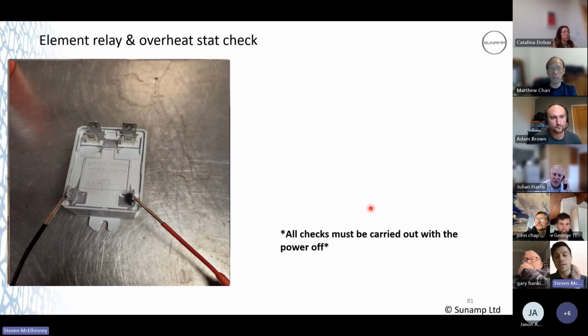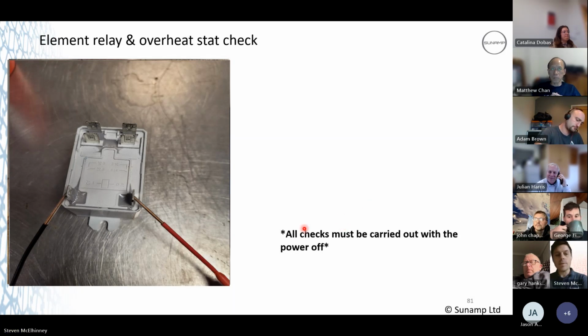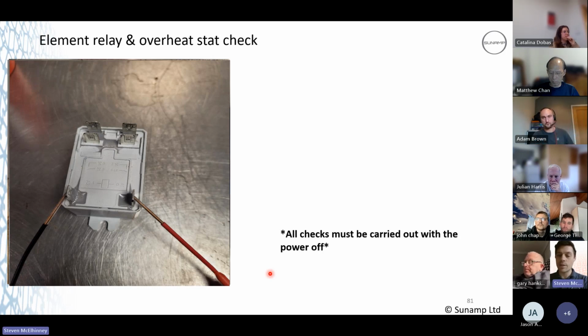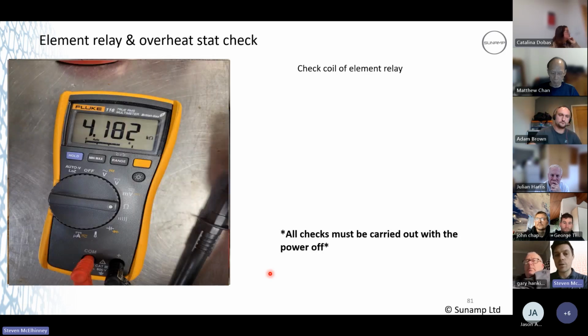Checking, so this is actually an AC relay. All our units now will be supplied with the DC. It's just in case you come across one of the older units, it may have a white relay in there, which is AC powered. So, how to check it? Obviously it's just got a coil in there. So if you're getting a problem with the customers not getting hot water, you suspect that it's not sending power, you can check the relay coil. You should be getting about 4 kiloohms across that coil.